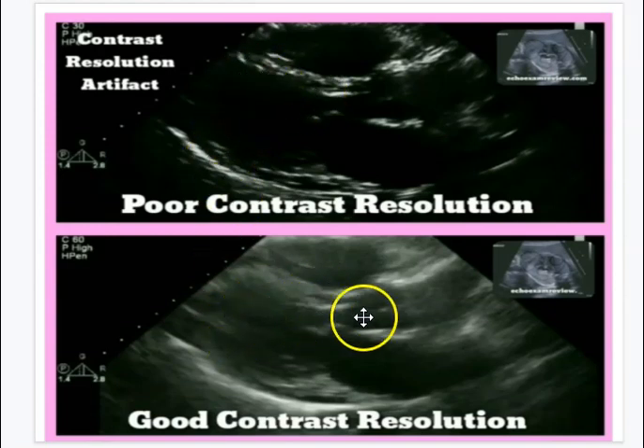So if we change our contrast resolution through grayscale, compression, or whatever, we can see we get much better contrast resolution here. And perhaps we changed our probe. Maybe went to a res setting instead of a pen setting or something like that. But this is considered good contrast resolution in comparison to that.